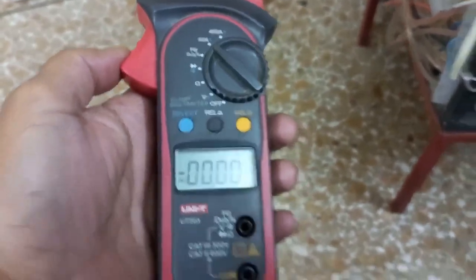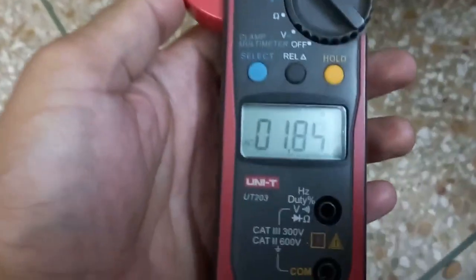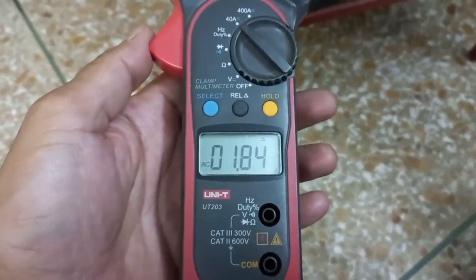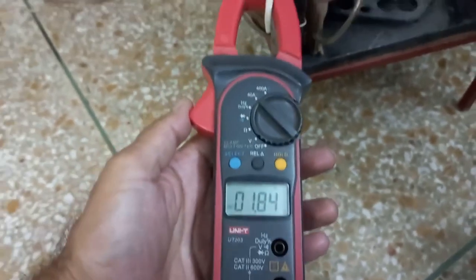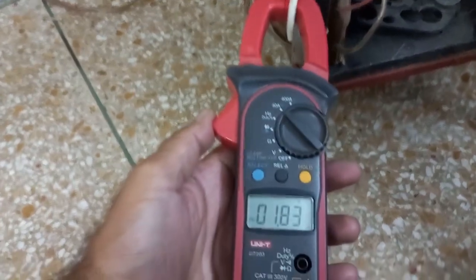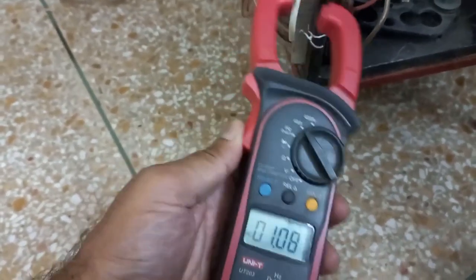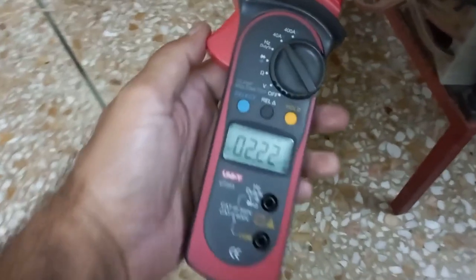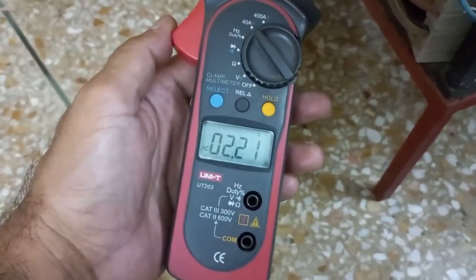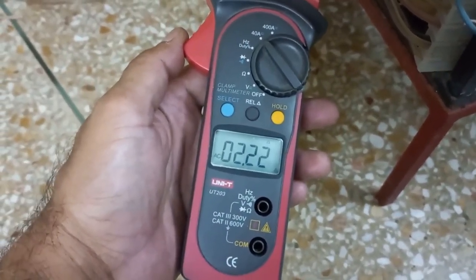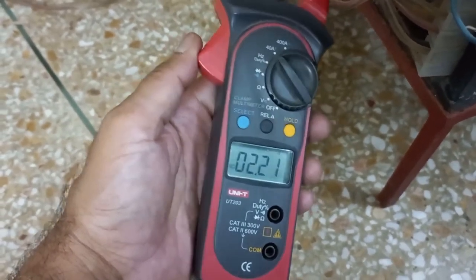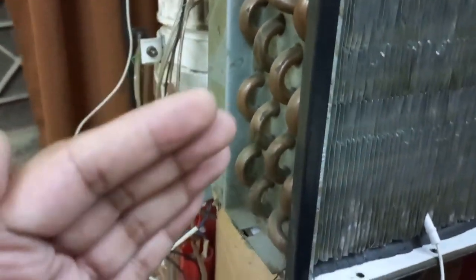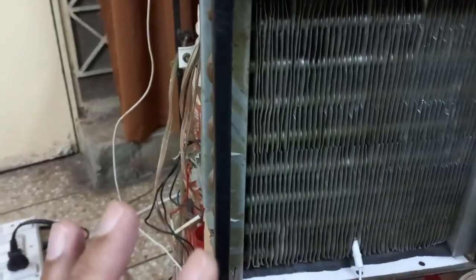Check the current here, AC ammeter, blown compressor, 1.84. The system has been running for more than 1 hour, maybe 1.5 hours. Total current is 2.2 ampere, same as before. Before it was 2.2, again it is 2.2, but it should be 2.3 because this fan is 0.1 ampere more. But as the system remains a little cooler, the compressor draws less current.